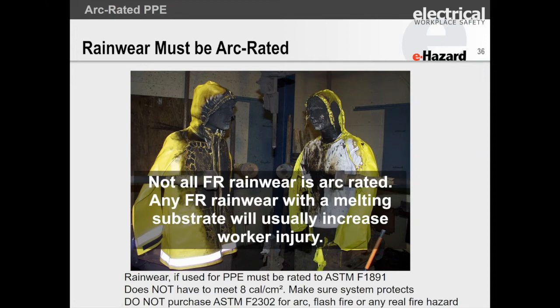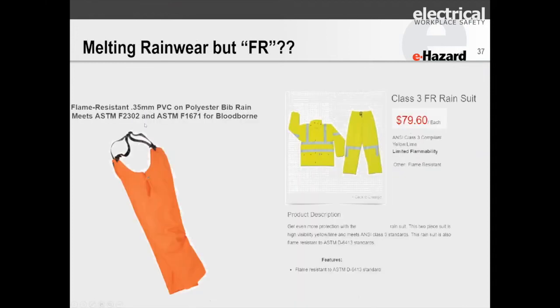A lot, especially up in the oil patch, there's a lot of winter wear from big name brand companies that claim to be FR. They have F2302 right in them. They're polyester batting. They're a rainwear that's been FR treated on the outside, and they will go up like a Roman candle in a flash fire or an arc flash, and they should never be worn by a worker thinking they're flame resistant. If they don't meet the arc standard, they will catch on fire at some level of arc, and they'll continue to burn and kill somebody. So these melting rainwear materials, these actually were from Canadian companies that we pulled out just to show you examples.